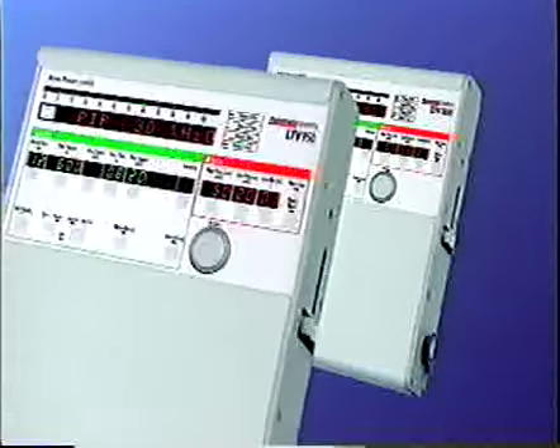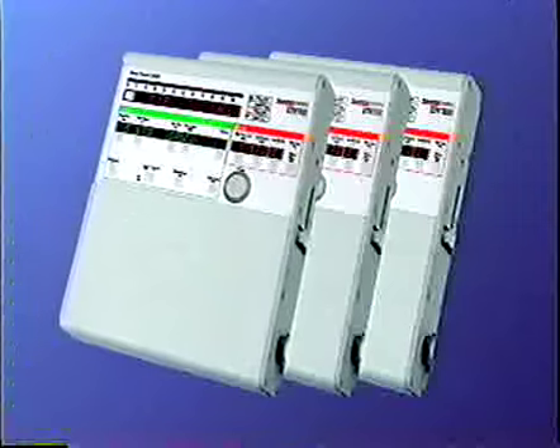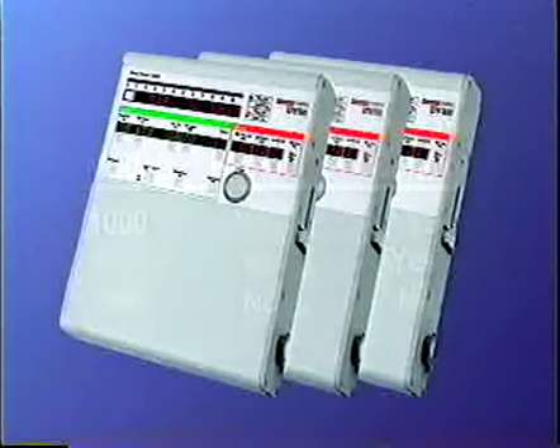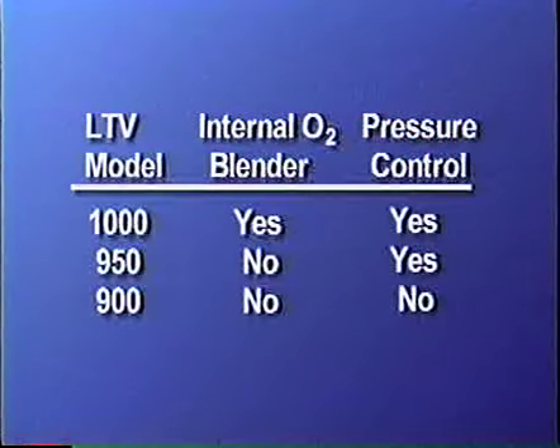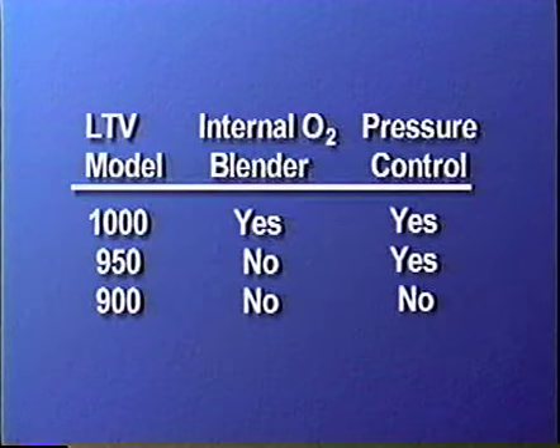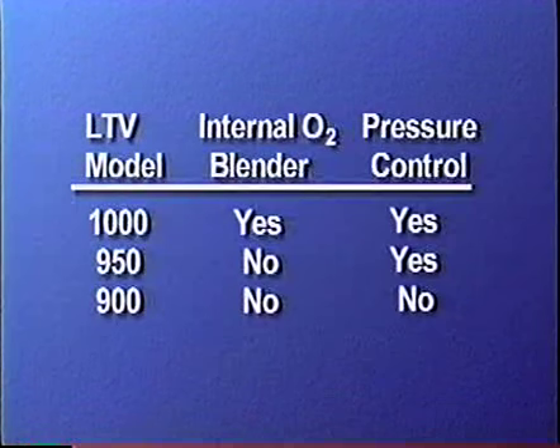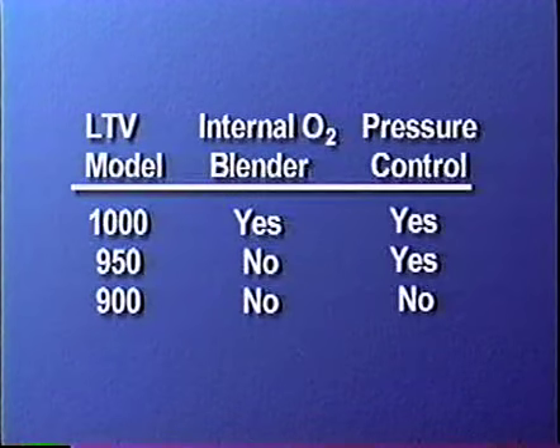There are three models of the LTV: the 1000, the 950, and the 900. The LTV 1000 offers an oxygen blender and pressure control ventilation. The LTV 950 does not have an oxygen blender, but does offer pressure control. The LTV 900 does not offer either an oxygen blender or pressure control.